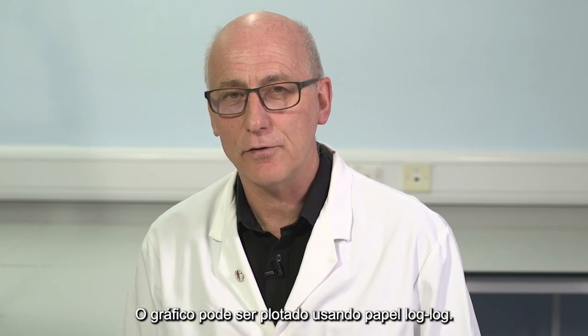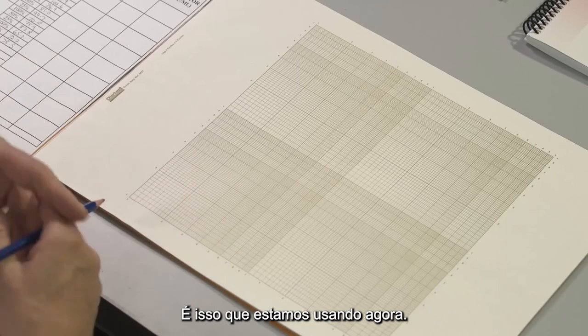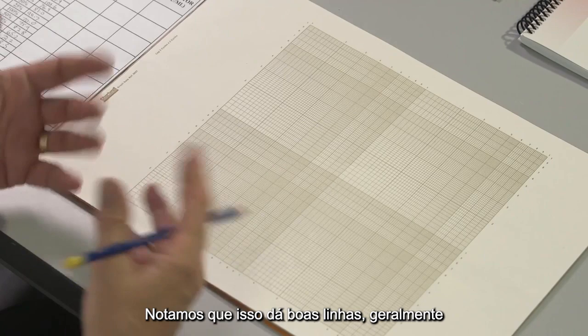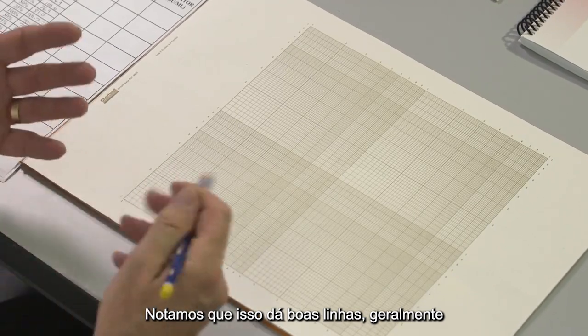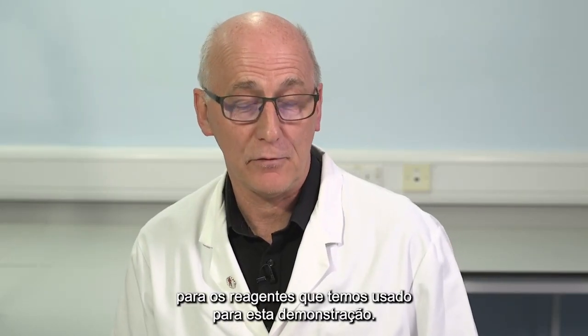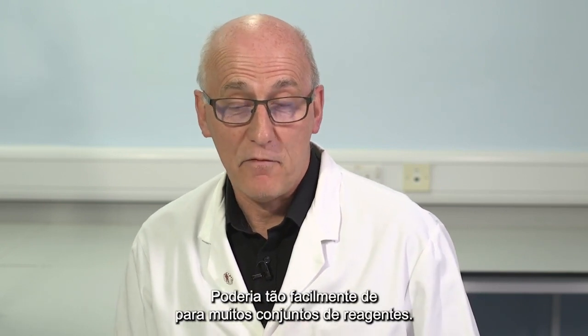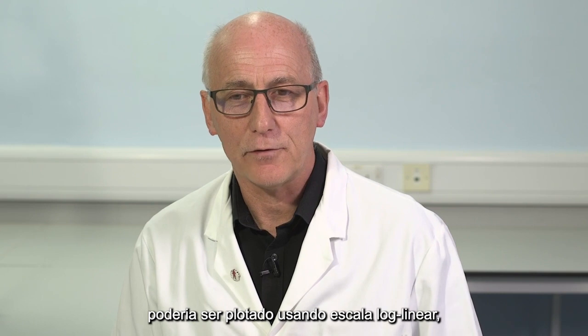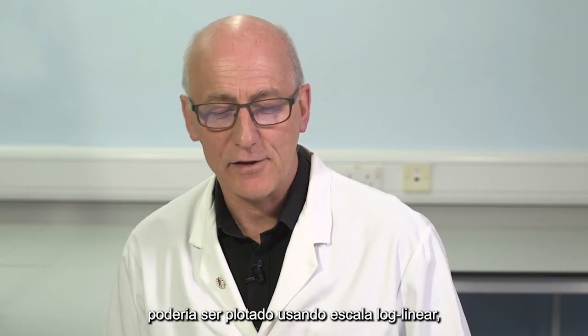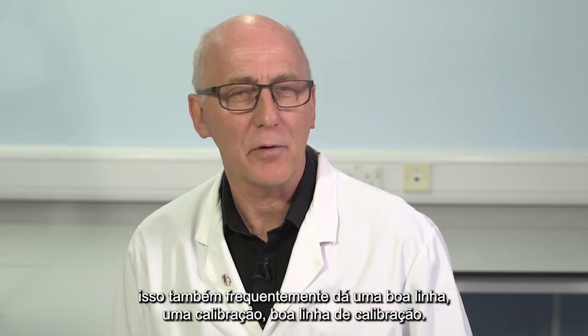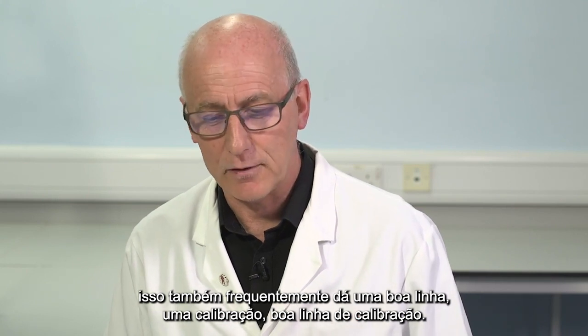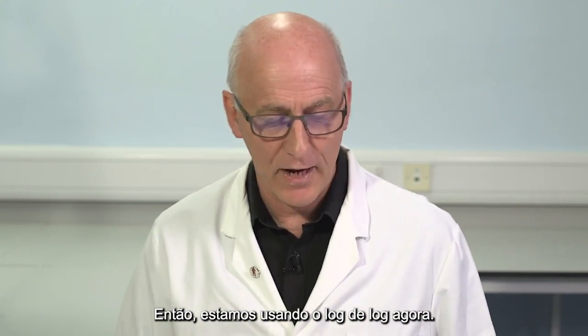So we need to take that clotting time to the graph paper. The graph can be plotted using log-log paper. That's what we're now using. We notice that this gives good lines usually, for the reagents that we've been using for this demonstration. For many reagent sets, it could just as easily be plotted using log linear scale. This also frequently gives a good calibration line. So we're using log-log just now.